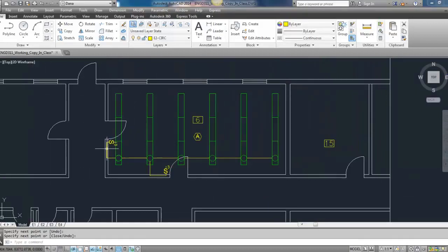The switching will actually go through the conduit into the luminaires from one switch to the other, and then it'll control all these lights at the same time. So when somebody walks into this room and turns on this switch, all of the lights come on at the same time. And as well, if somebody were to exit using this door, they could turn all the lights off using the switch. So they all have to be connected through the junction boxes for those luminaires.